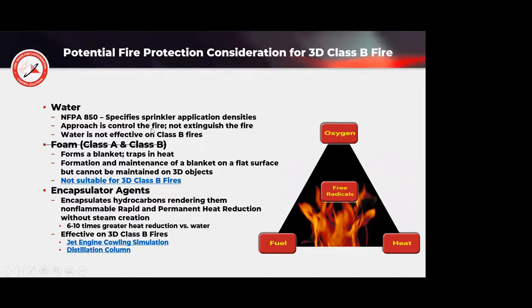The approach is to control the fire, not to extinguish the fire. We certainly know the plain water is not a good fire extinguishment agent for Class B. If it was, we never would have invented foam, and further wouldn't have invented encapsulator technology. So it's not effective. When we look at foams, foam forms a blanket. It's not conducive to these three-dimensional flowing spray fires.